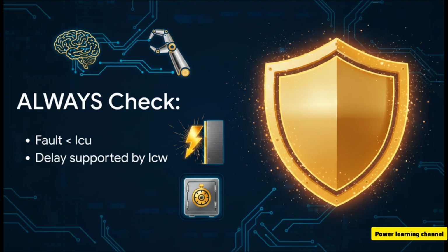First, the actual fault current must be less than your ICU. Second, if you program a delay using your S function, that delay time and current must be fully supported by the breaker's ICW rating. Remember, your brain's clever logic doesn't matter one bit if your body's physical strength cannot actually survive the fault or the delay time.